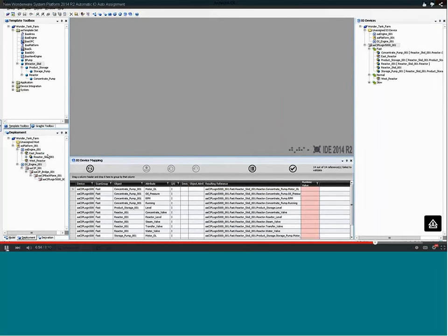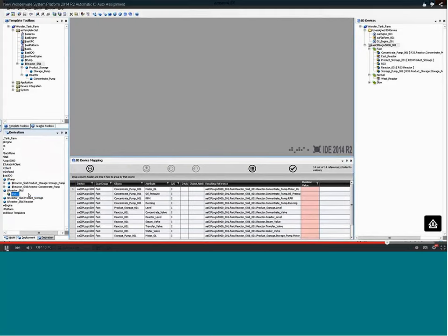So you can see that the references failed, and that's because I forgot to change the name of my object to match the name of my PLC. So I'm going to go ahead and do that. The name of my PLC is actually R33. I'm going to change that, apply my overrides, and validate. You can see now that everything validated, I've got all my values coming directly from the PLC, and I didn't even have to deploy these equipment objects. You can see that I applied that override to R33 for the name of my parent object.